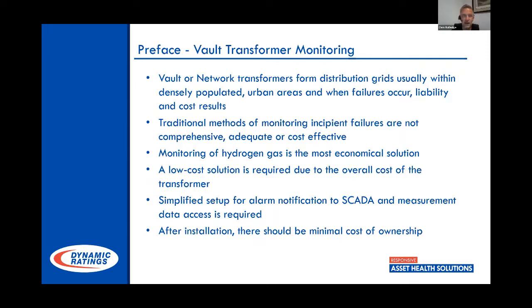I can't tell you how many times I've been in a vault where a cable compartment had developed a leak and all the oil had run out on the ground. I mean, you don't have a lot of clearance in there. You need that dielectric, so any moisture ingress is really exacerbating the chance of that failure happening.